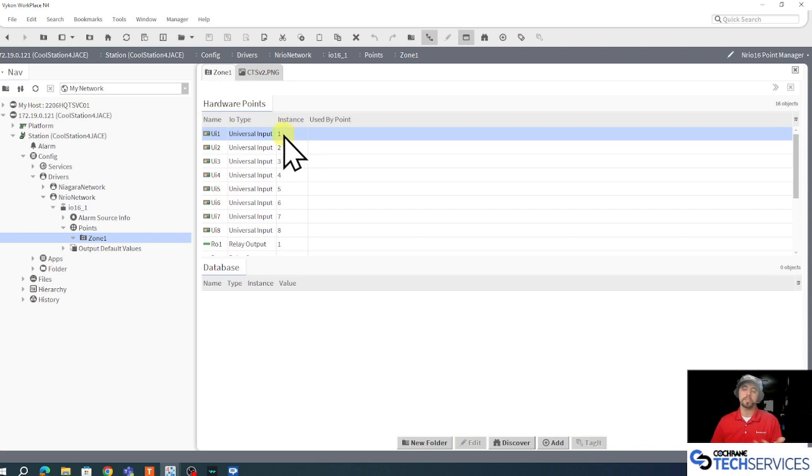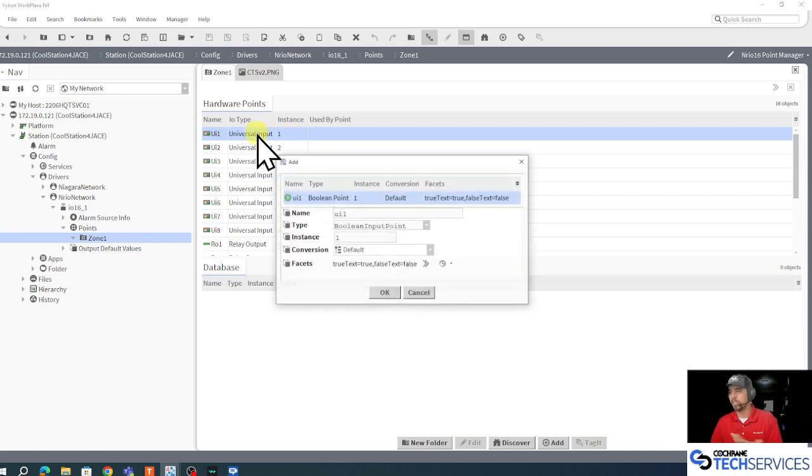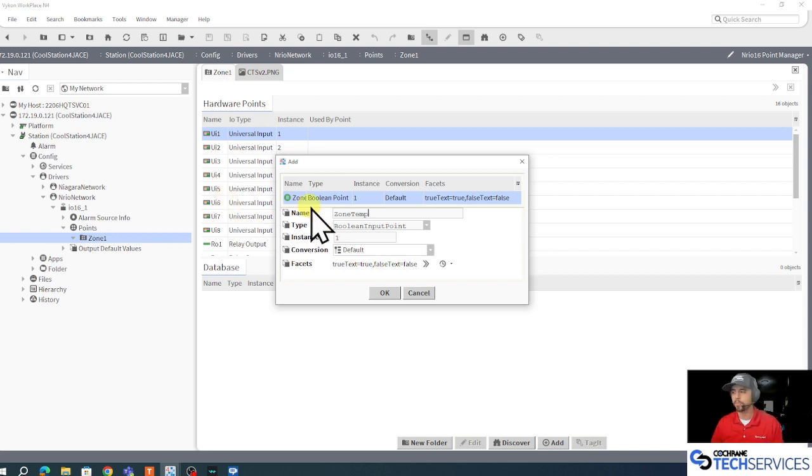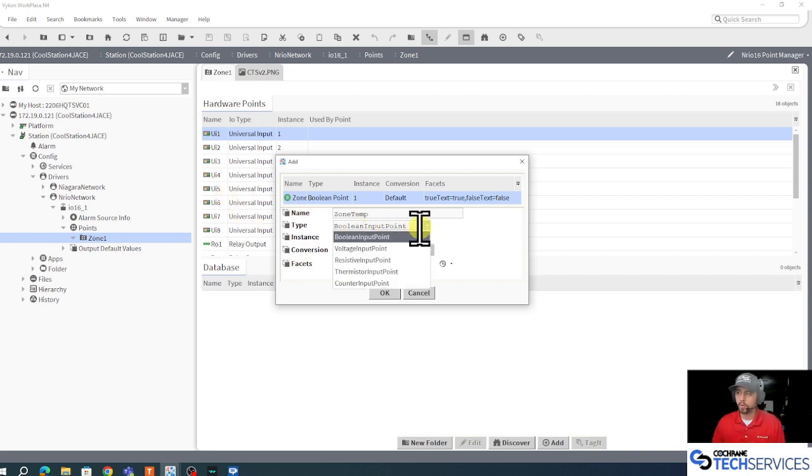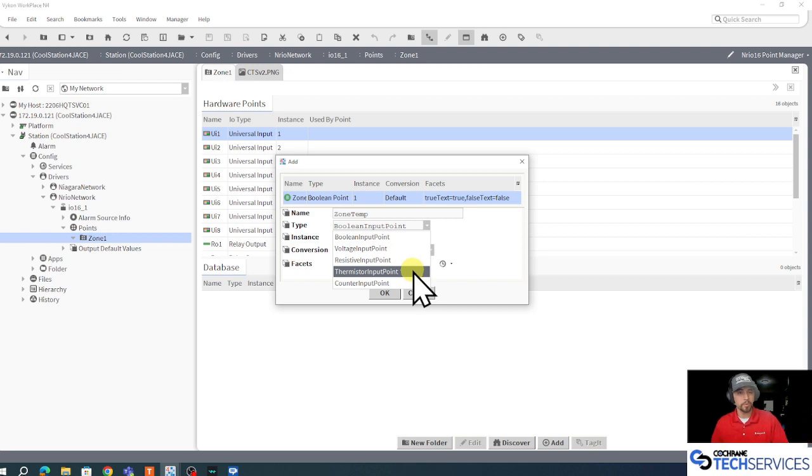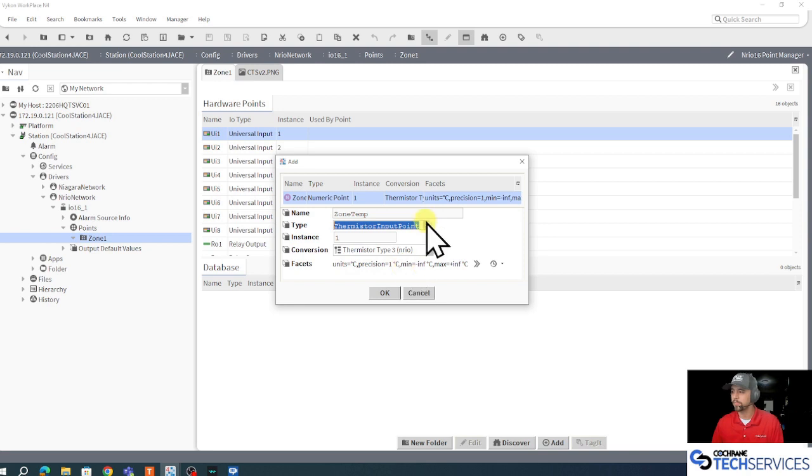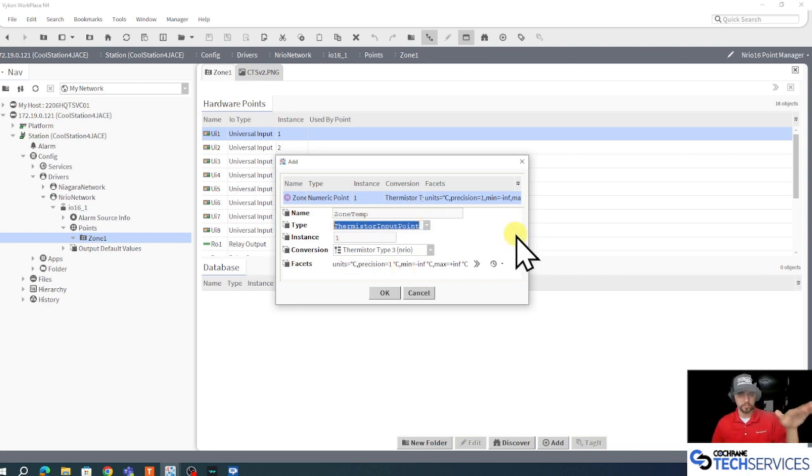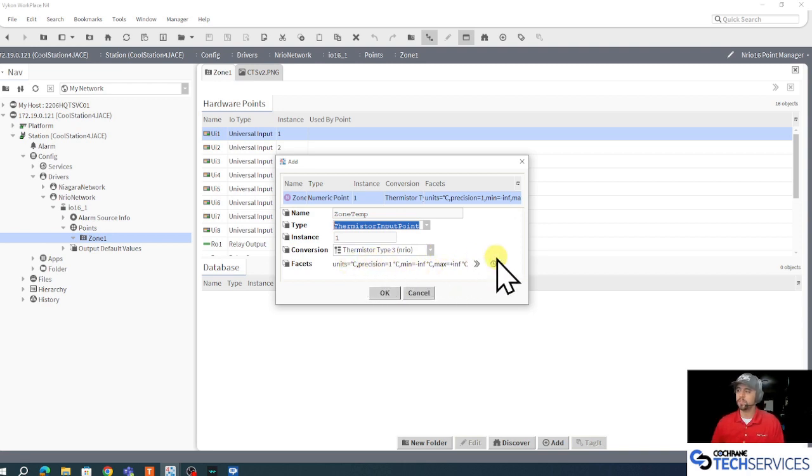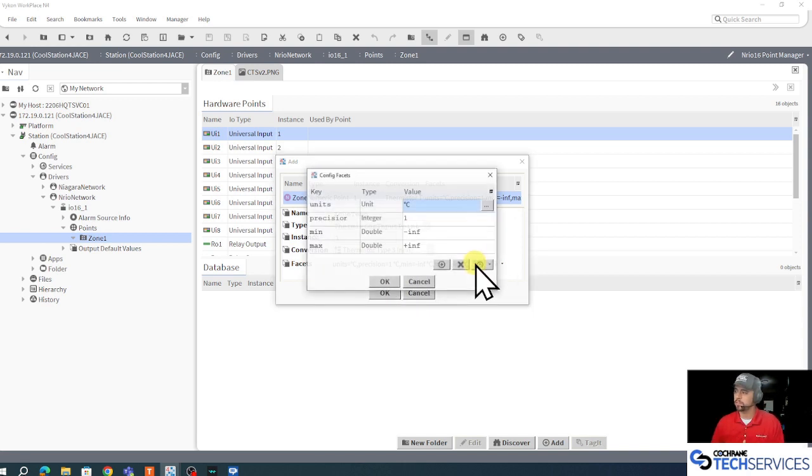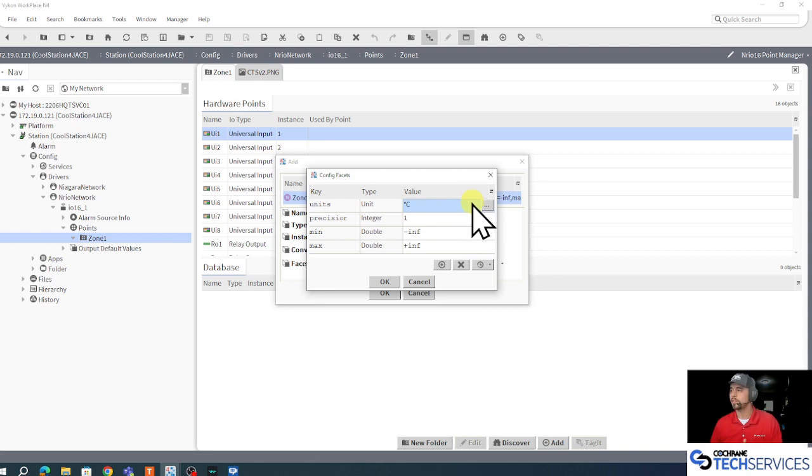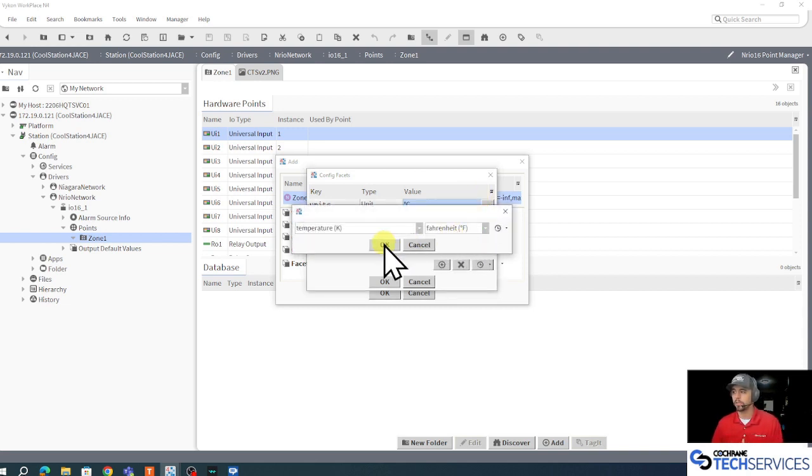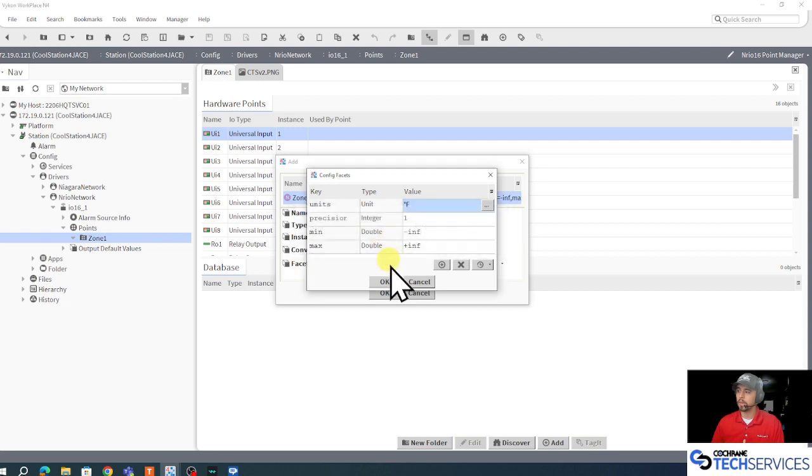So let's say my zone temperature sensor was UI1. To add it, I would just double click UI1, I would name it something appropriate, in this case maybe zone temp. And it certainly is not a boolean type of point, it's actually a numeric point, and specifically it's a thermistor input for our IO 16 device. So I want to pick my thermistor input which should be that natural curve like typical thermistors are. Here's a thermistor type 3, and instead of using degrees Celsius, I'm going to hit my little chevrons and I'm going to change my facets to degrees Fahrenheit. I'll click OK a couple of times here.